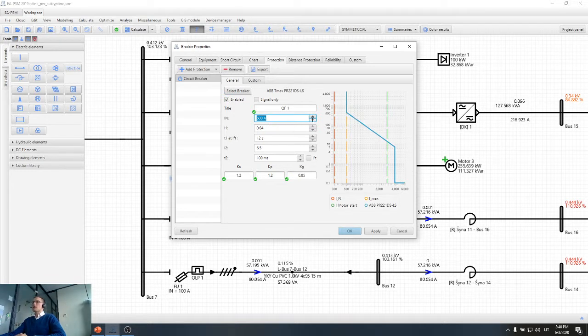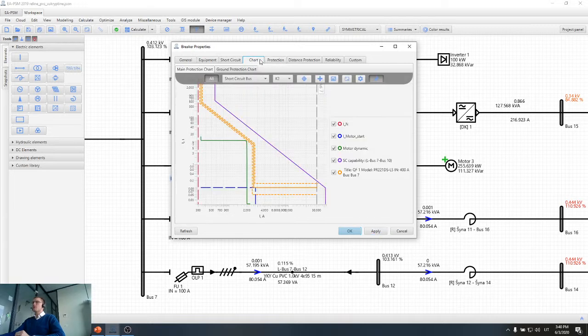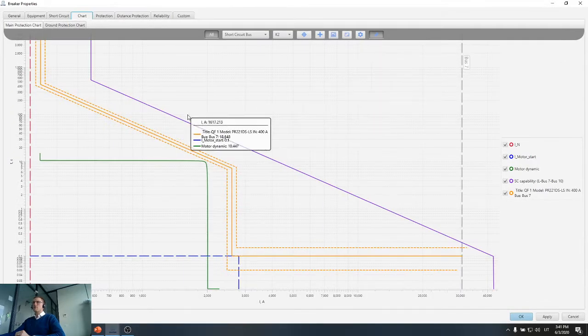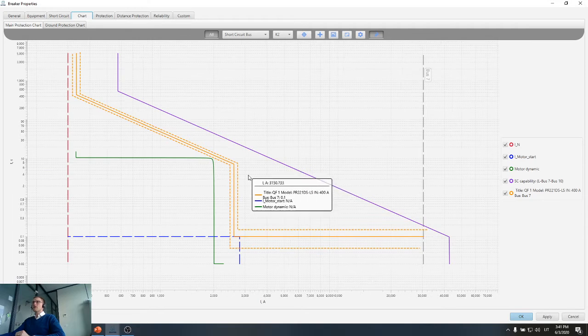First we need to select the nominal value for the breaker, and one possible option would be to select 400 amps nominal, which I think should be enough. Then we can see that it is possible to select current multipliers and time settings for the breaker. These current multipliers and time settings are very important, because they specify how our breaker will operate. So let's check what settings we should provide for this specific breaker. I will go back to the chart curve for this breaker.